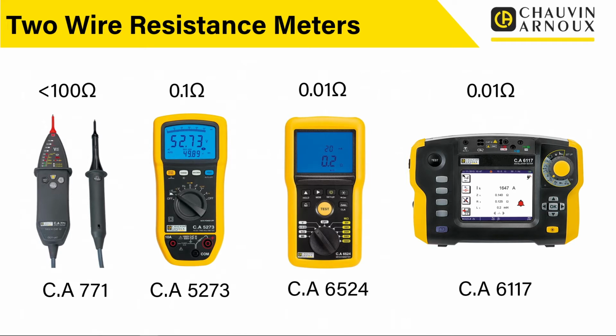Now, where quite often there's a bit of a crossover is when we get to our electrical installation testing, BS 7671 and other standards like that. We get into this region where generally to carry out those sorts of tests, the specified measurement range is really down to 0.01 ohms. So we're reading down to 0.01 ohms when we're doing things like our R1 plus R2 tests, or checking our main protective bonding conductors maybe. So you could be using a multifunction tester like our CA 6117, or maybe a standalone insulation continuity tester like the 6524 there. Both of these employ a 2-wire measurement, and both of them will only really get down to that 0.01 of an ohm. And actually, this is where I think there's a bit of a gap in the market really.